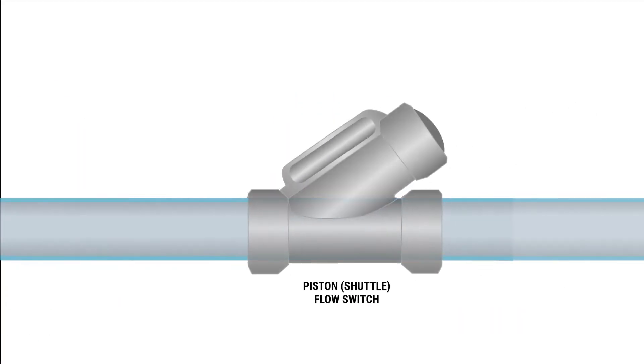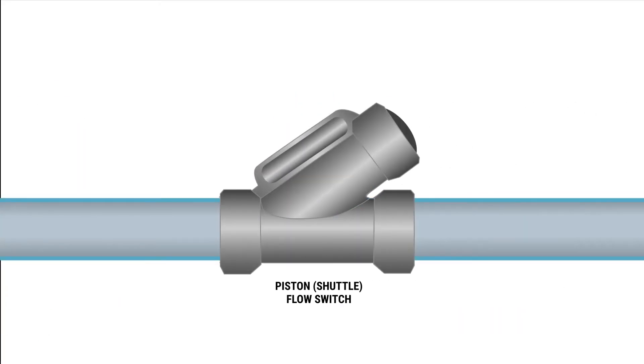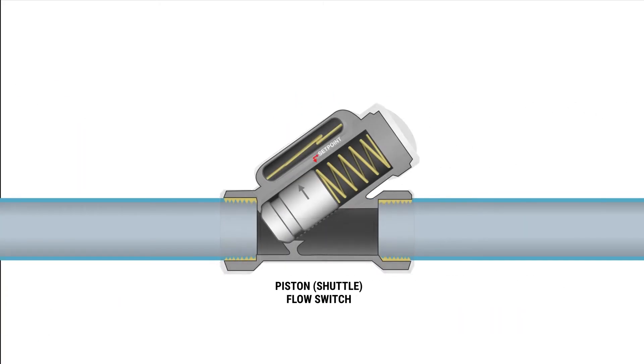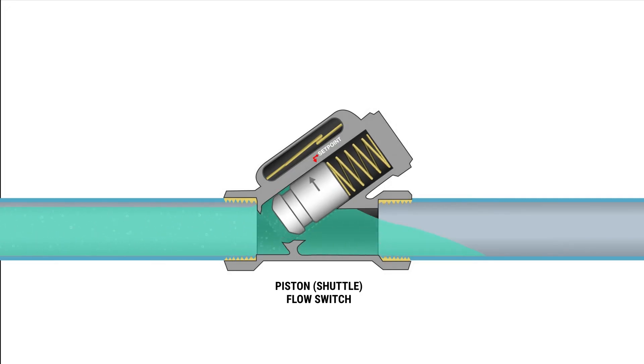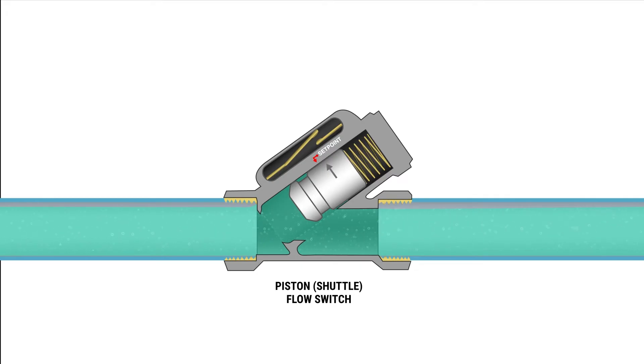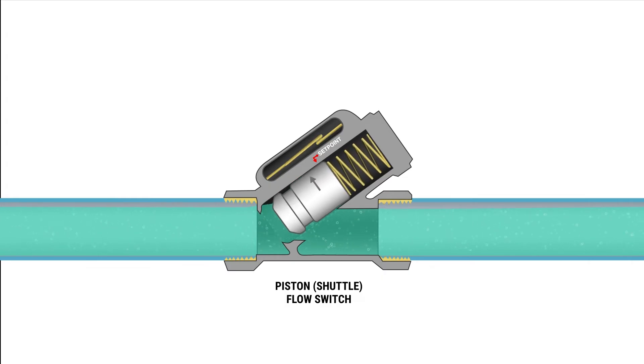Next we have the piston or shuttle design flow switch. With a piston type flow switch, a free-floating magnetic piston responds to the amount of flow within the line. When there's an increase or decrease in the flow rate, movement of the piston actuates a hermetically sealed reed switch, triggering the specified action.